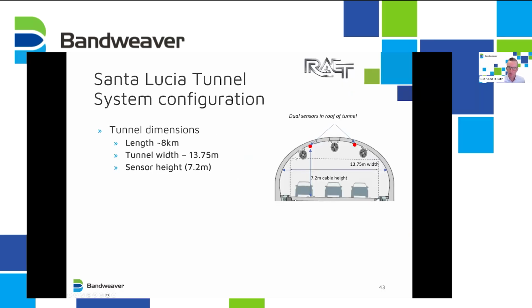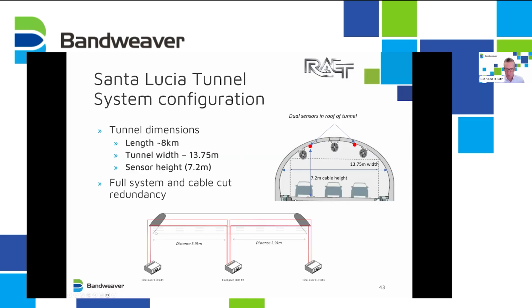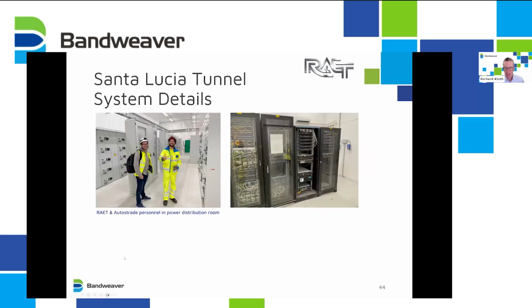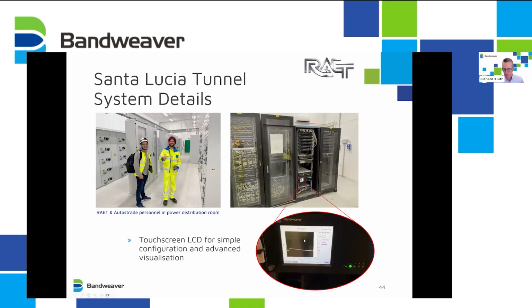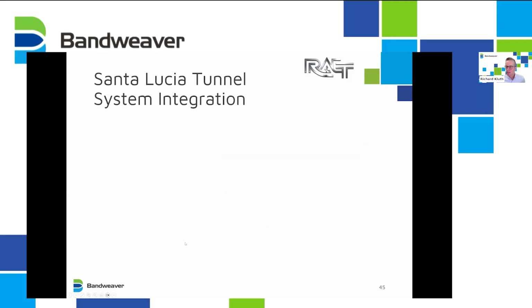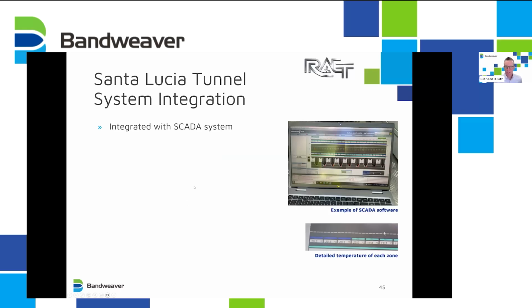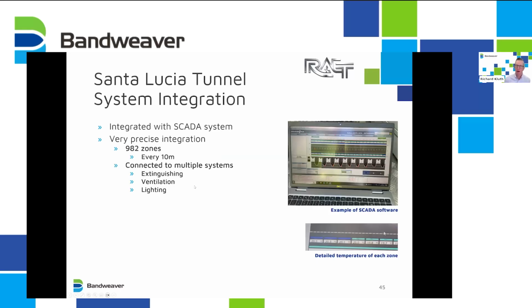So this is the Santa Lucia tunnel, which is the widest tunnel in Europe, nearly 14 meters wide, and has 2 cable sensors on the roof. We monitored 8 kilometers with 3 systems to give full controller and cable redundancy. You can see an example here of the team in the substation, the unit in the rack, the touchscreen LCD. So again, this was integrated with the SCADA system, and this is one of the most advanced I've seen, where they set up zones every 10 meters, so 982 zones connected to multiple systems, including extinguishing, ventilation and lighting systems.